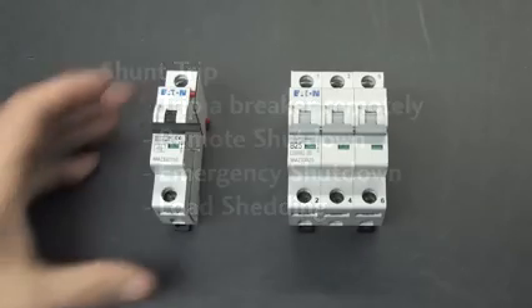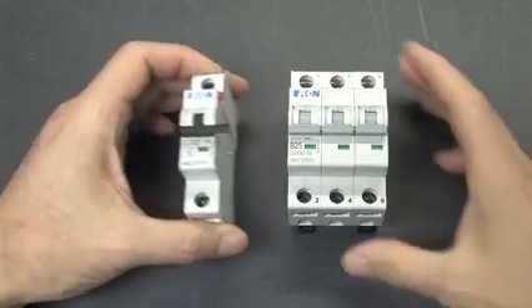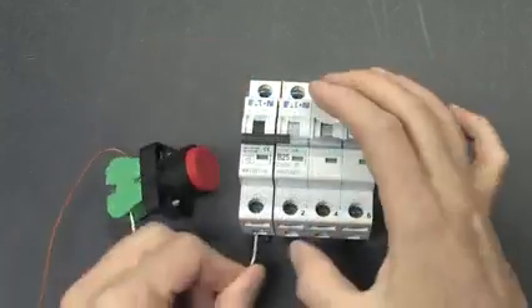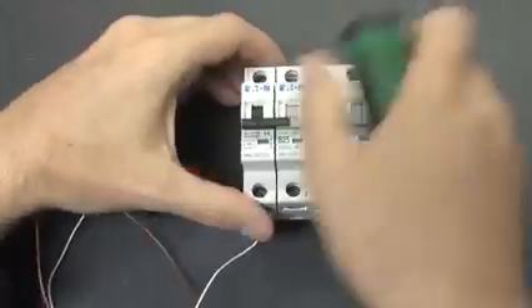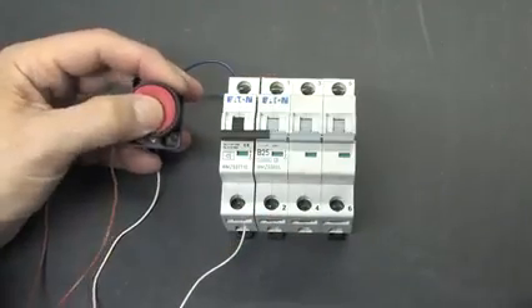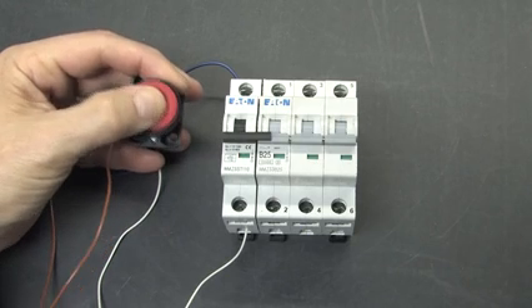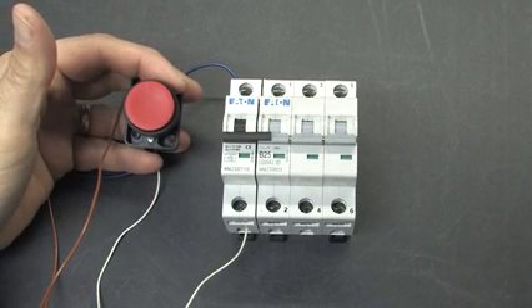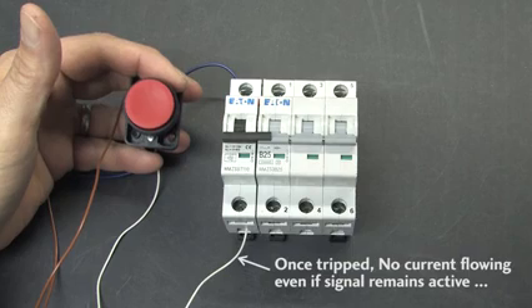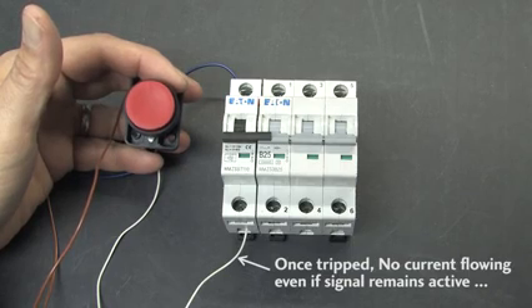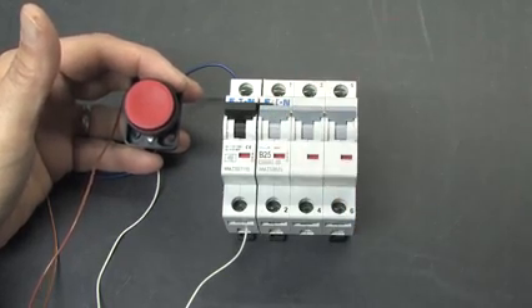Sometimes you want to safely trip a breaker remotely. That's what a shunt trip is for. It's basically a cheap way to provide remote or emergency shutdowns, or even just a way to automatically shed loads. Here's an example of an MCB shunt trip. You attach it to the breaker, and then you wire it to a PLC output, or even just a manual switch like I have here. Now you can remotely trip the breaker without opening the cabinet. Once tripped, this device typically disconnects itself electrically, so there's no current flowing through the control wires. And you have to manually reset the breaker after it's been tripped.